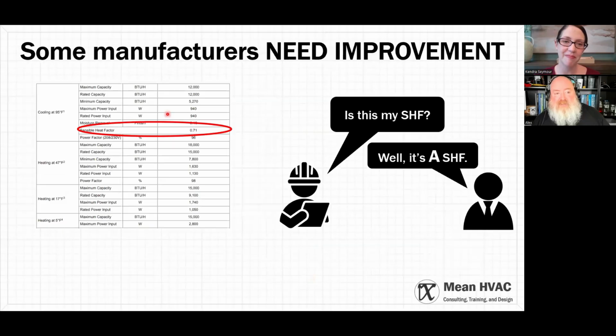And so they dumb it down and they sell crappy stuff sometimes. Some are better - like this is a major brand, and at least it gives me how good it is at humidity control, but only at its full capacity. It doesn't tell you - it's not the sensible, they call it the sensible heat factor, what's the percentage that's sensible and how much is humidity. That's one of them. What happens when it's only running at 80%? Well, we're not telling, we don't publish that data.